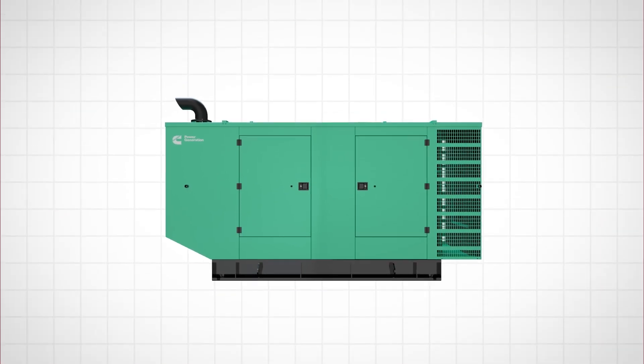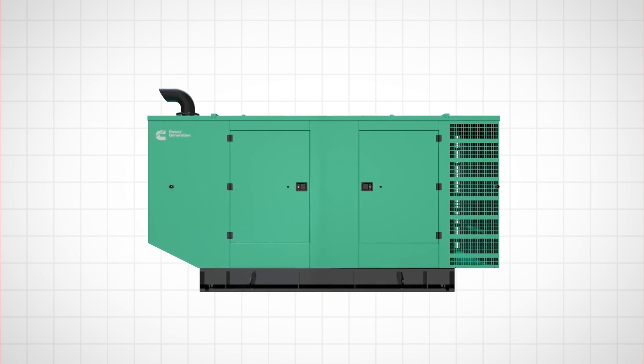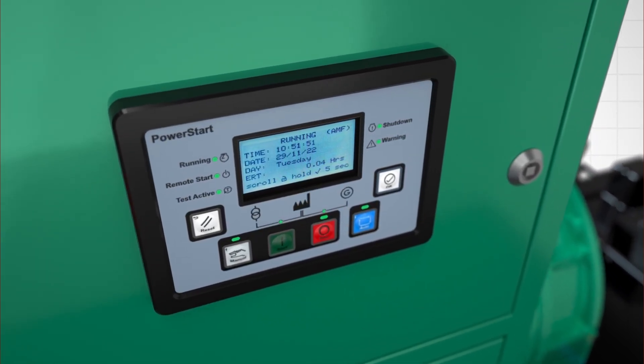As we do this, we look at every subsystem of the genset in detail and tailor it to meet requirements. Take the enclosure design: we did a boltless design which delivered better aesthetics. These enclosures prevent water ingress and can withstand wind loads of almost up to 100 miles an hour. They are compliant to noise levels of 85 dBA at 1 meter, and the gensets have demonstrated a limiting ambient temperature capability of 50 degrees Celsius.